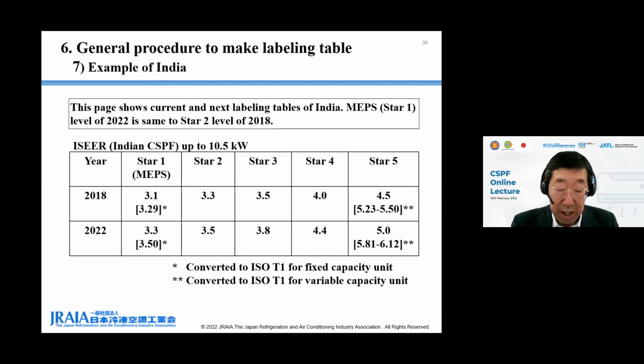Star 1 level 3.3 and star 2 level 3.5 in the new 2022 label are same as the star 2 and star 3 levels in the old 2018 label. Star 3 level 3.8 and star 4 level 4.4 in the new 2022 label are a little lower than star 4 level 4.0 and star 5 level 4.5 in the old 2018 label. This may be based on the current CSPF distribution in the Indian market. Star 5 level 5.0 in the new 2022 label is newly set at higher level. Next, please.